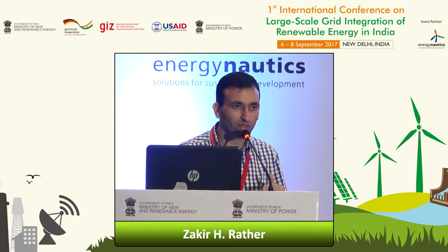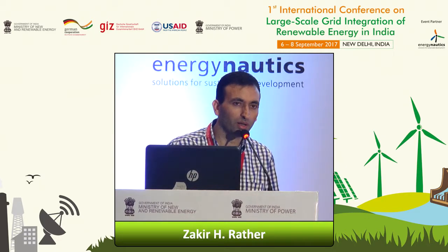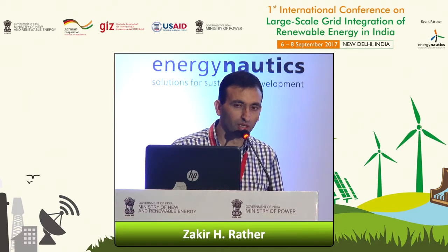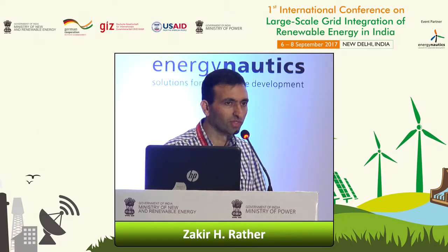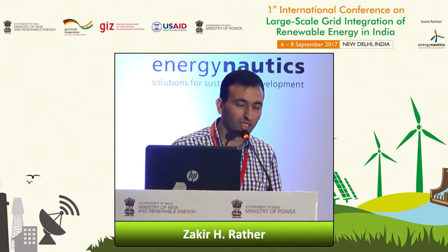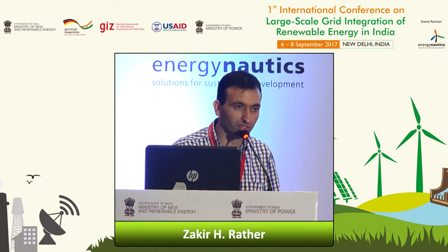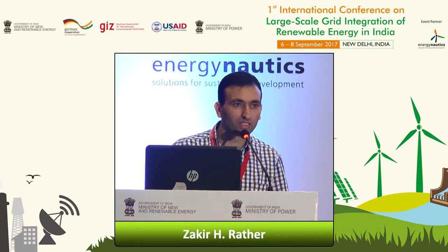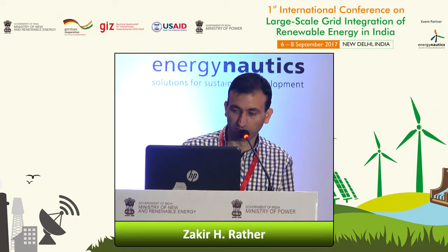The issue here is that we have diminishing inertia in the system due to more and more wind integration. Can we try to support the system with fast frequency from wind turbines? But a bit of a difference here is that we are trying to use this service primarily for fault events, voltage events, rather than direct frequency events. As I mentioned in one of the first presentation slides, a fault can lead to a frequency event in a wind-integrated system. So can we get support from other wind turbines which are less affected during the fault, to support the grid while maintaining their connection to the grid?